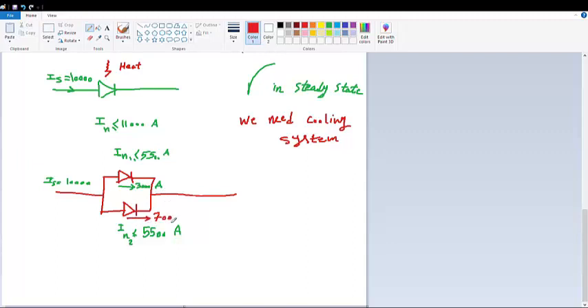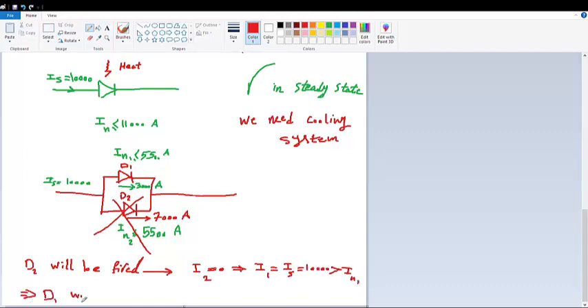Now we want to see what happens if the parallel diodes contribute with different current values. One of them takes 7,000 amps and the other one 3,000 amps. As a result, the first one damages due to higher current than the rating current. Immediately, the second one has to take all 10,000 amps and therefore fails afterwards.